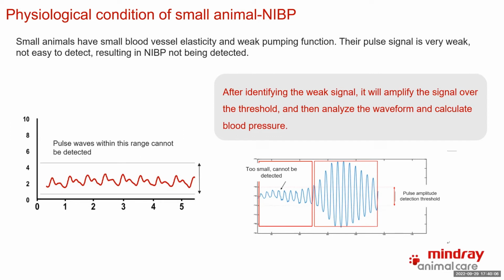So for our machine, when we detect their signals are very weak, we will amplify the signal to over the threshold, and then analyze the waveform and calculate the blood pressure. So that's the reason why even when we monitor some small animals, we can still get accurate NIBP readings. So you can see, from ECG to SpO2 to NIBP, we have the algorithm and it's optimized for the animal applications.